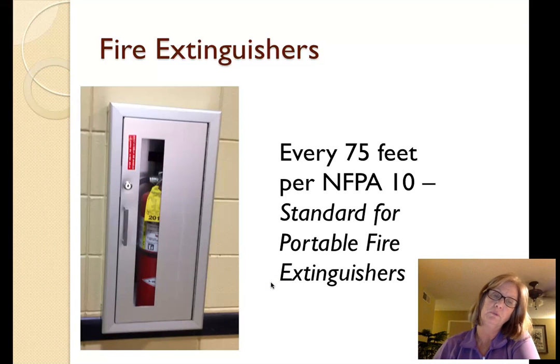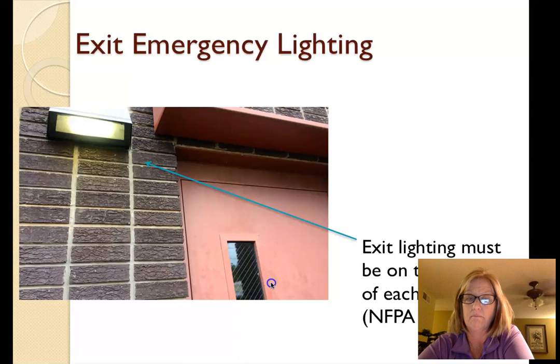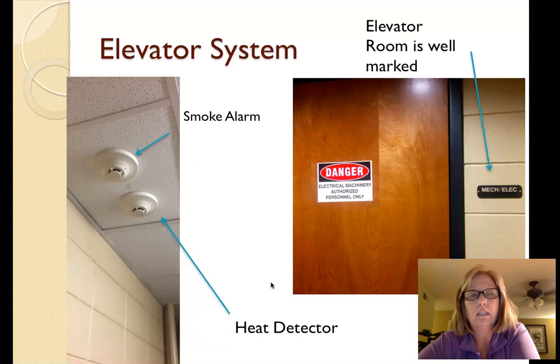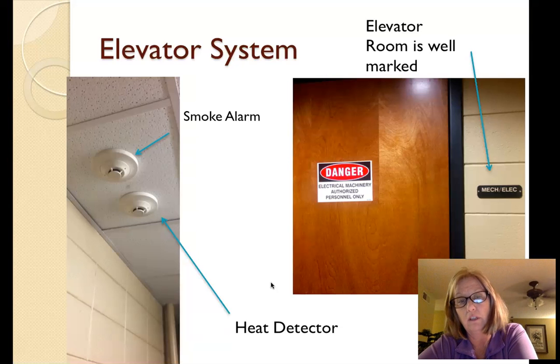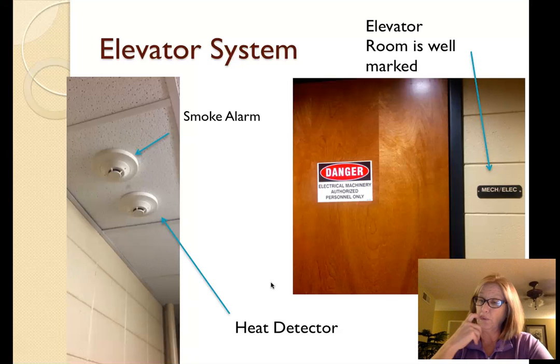The fire extinguishers were placed every 75 feet per NFPA 10 standard for portable fire extinguishers and were due to be inspected this month. Emergency lighting was positioned throughout this building on the inside and outside of the building. This is per NFPA 70. The elevator is in the front entrance and is a hydraulic elevator. It has to be, according to NFPA 13, sprinklered in the elevator shaft, at the front of the doors on each level, and in the elevator room.